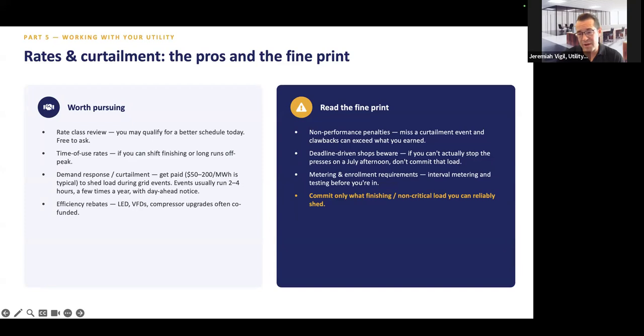But you've got to read the fine print. If you don't perform during a curtailment period—usually the utility emails you about 24 hours ahead, sometimes just a few hours—they say they need you to pull back some of your energy because the electric grid is overloaded on a hot day, and they need your energy to supply other buildings. If you don't meet that curtailment, there's a non-performance penalty, and those penalties are brutal. Every contract with vendors in a curtailment program is different.